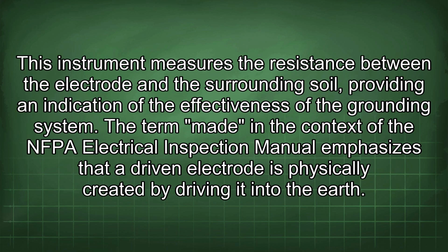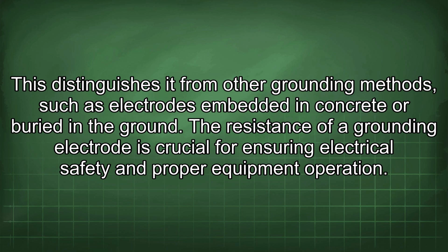This instrument measures the resistance between the electrode and the surrounding soil, providing an indication of the effectiveness of the grounding system. The term "made" in the context of the NFPA Electrical Inspection Manual emphasizes that a driven electrode is physically created by driving it into the earth. This distinguishes it from other grounding methods, such as electrodes embedded in concrete or buried in the ground.